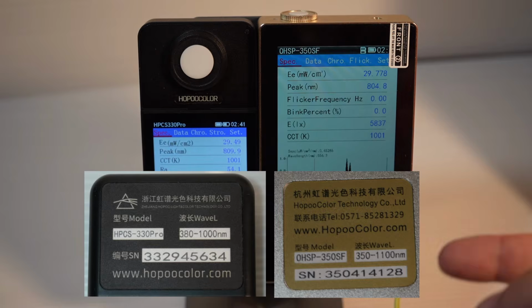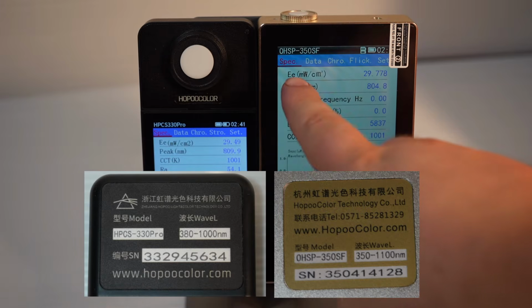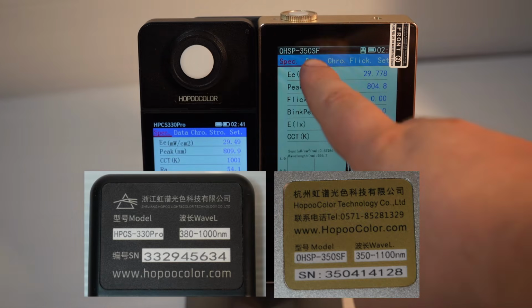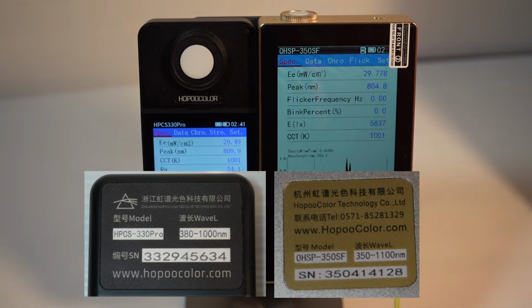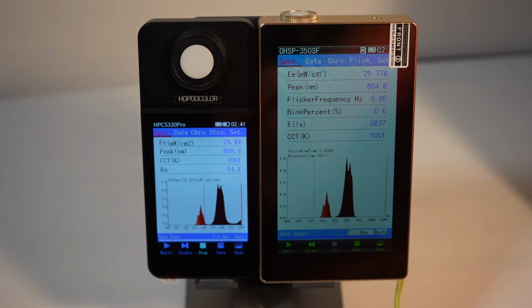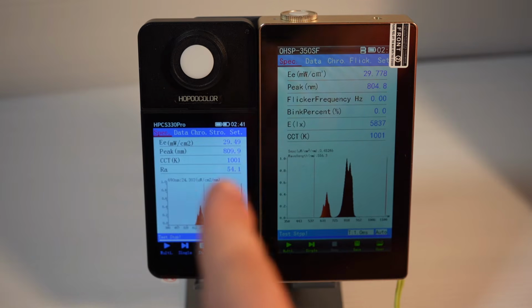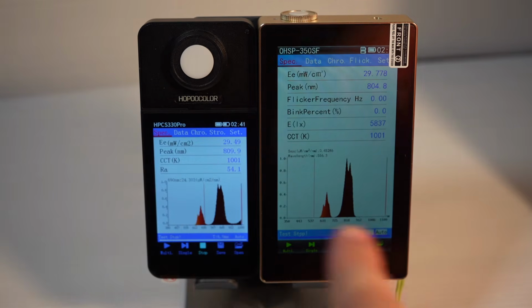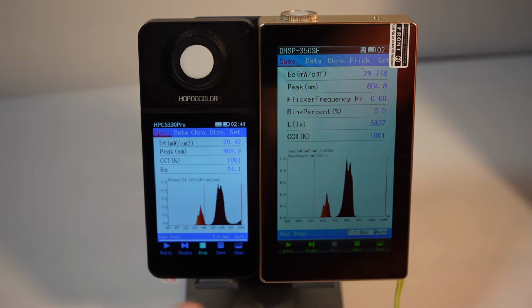And it's manufactured by the same brand, but it's the OHSP-350SF model. But you can see here from the display, the functionality is very similar. You can measure the intensity in milliwatts per centimeter squared in both, and they tell you the spectral distribution, which you can download and really analyze the peaks in the spectrum if you want. Except the cheaper one is a bit smaller.